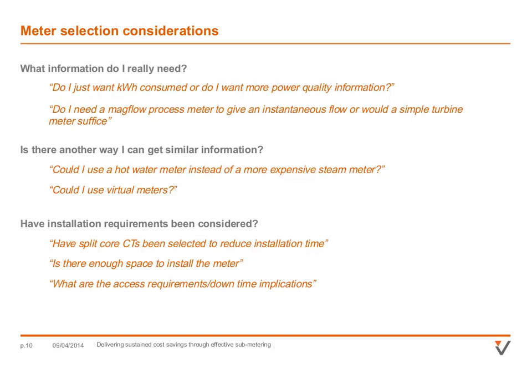But it's basically for an electricity meter, you have a current transformer. It's basically a lump of metal which changes a current from what's going through a cable to something the meter can read. It's a loop or continuous loop of metal, sometimes a square, and that has to go round a cable. They can come as solid core, meaning you have to detach the cables and put them through, or split core, meaning you can clamp them round, which makes installation - certainly on existing plant - a lot quicker.